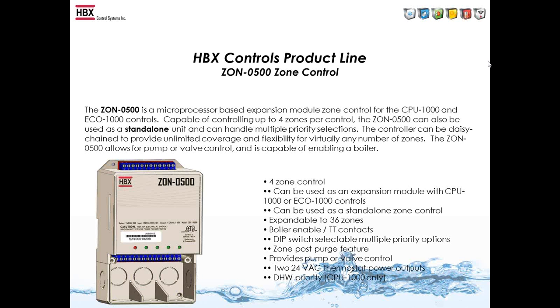It's dip switch selectable on the back whether you want to run a high temp demand or low temperature demand zone. So this will fire the demand on the control when the zone either calls for heating or cooling. In warm weather shutdown, it will send the signal from the 1000 control to the zone control to shut off the zones. So if there's a thermostat calling and the control's in warm weather shutdown, it won't turn the pump on, which gives you a lot better efficiency.